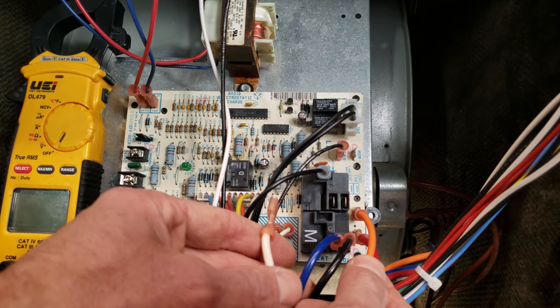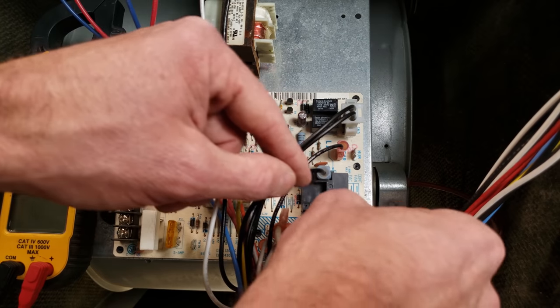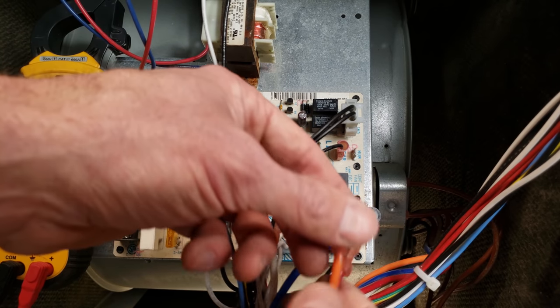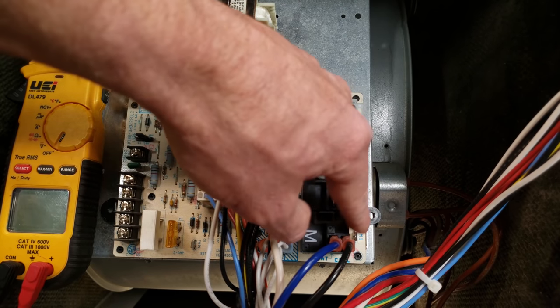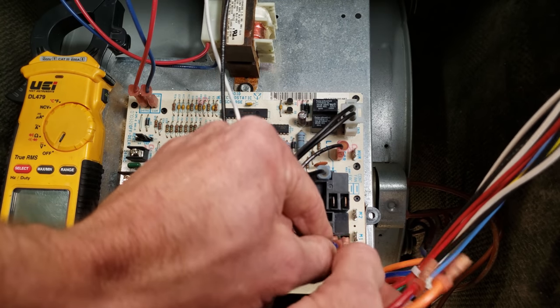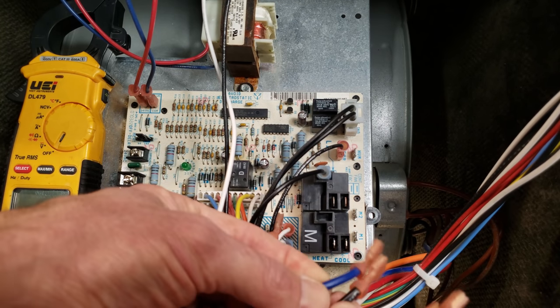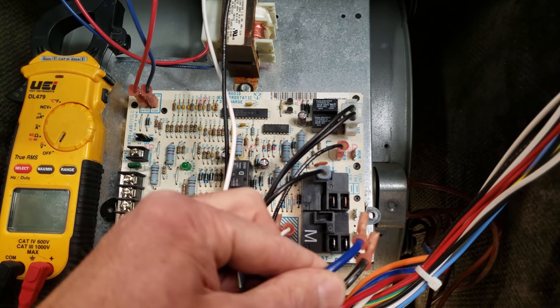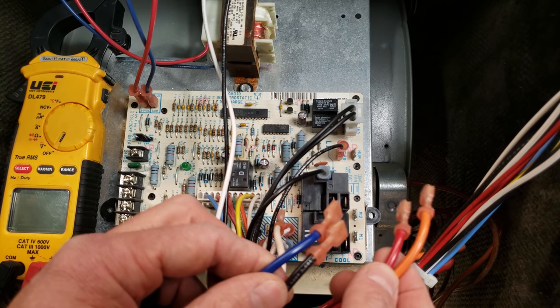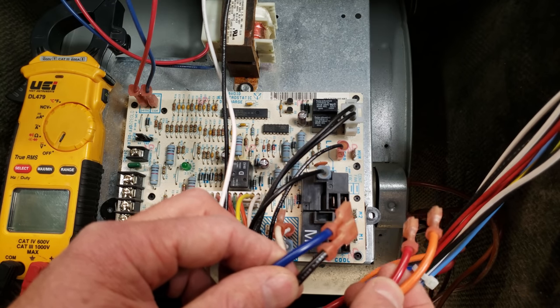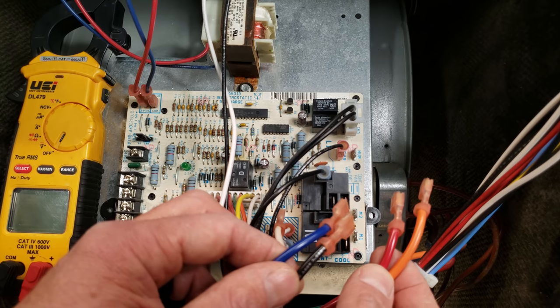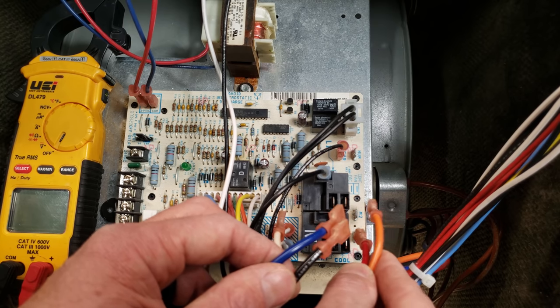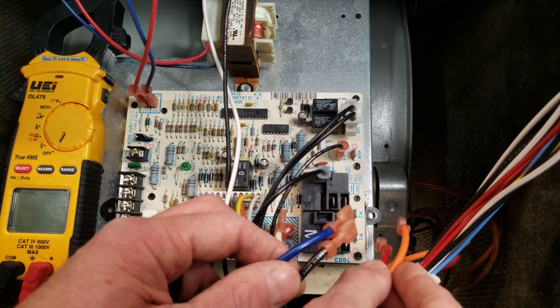Two are on the spare terminals, which are listed as M2 and M1, or they may be listed as spare, and then there's two additional speeds right here. The ones on the spare are not going to be used for the blower motor speeds, but you need a safe place to put them so they don't back feed any voltage onto a ground and short out the blower motor.